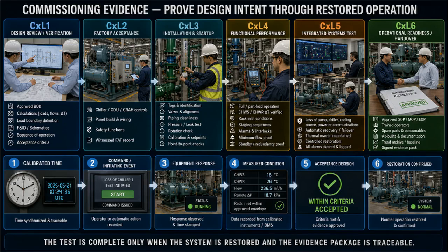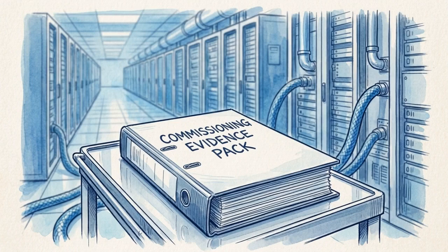Normal mechanical lineups are confirmed, manual overrides are closed, standby assets are verified available, and all time-aligned evidence is signed and archived. A resilient cooling system exists only if proven under stress. Without auditable, time-aligned evidence demonstrating recovery, thermal design intent is just a theory.